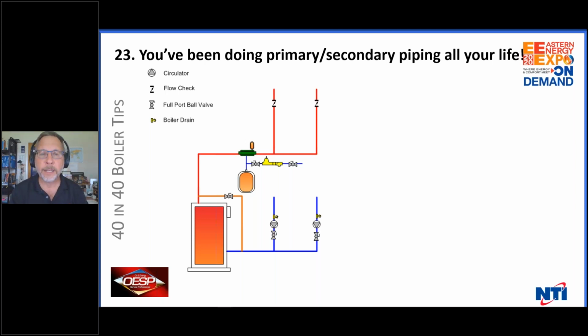We put a bypass on it, didn't we? Isn't this primary secondary circulation? Because if we think of the definition of that, when the boiler can have one flow and the system have another flow, that's primary secondary circulation. And all we did by putting the bypass in is bypass the boiler so the boiler could get out of condensing mode and get up to temperature, and the system could come up on temperature slowly so things didn't tick, tick, tick, tick all over the place, and everything worked harmoniously and the boiler didn't condense because you didn't want a cast iron boiler to condense.